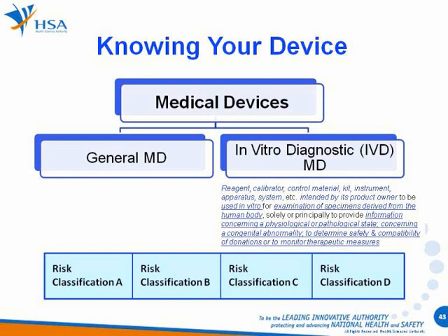Next, you will need to determine if your product is a general medical device or an in vitro diagnostic medical device. An in vitro diagnostic device is any instrument, reagent, etc. intended by its product owner to be used in vitro for examination of specimens derived from the human body.